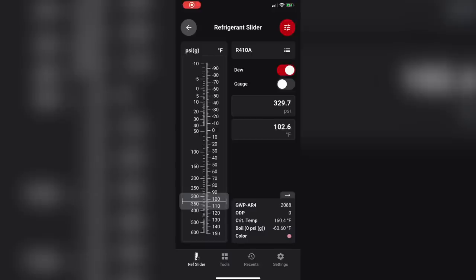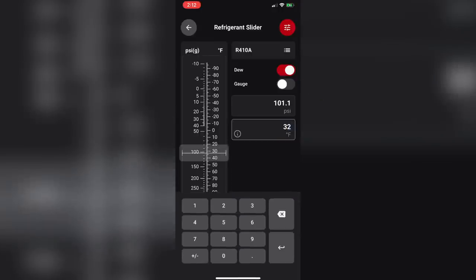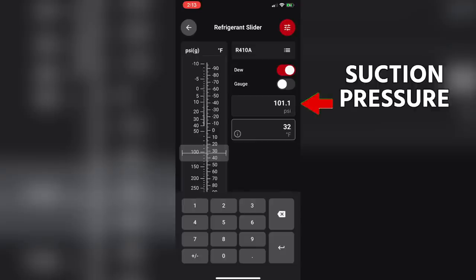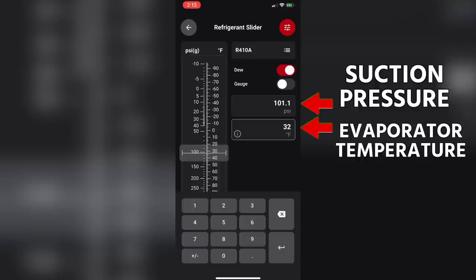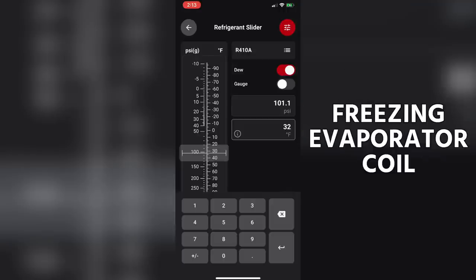When we think about that 32 degrees, that is a 32-degree saturation temperature. Using the Danfoss refrigerant slider app set to gauge pressure, you set it to 32°F and you can see that's 101 PSI. So if a system runs below 101 PSI suction pressure — which equates to a 32-degree evaporator or suction saturation temperature — for long enough, that's going to result in a freezing evaporator coil.